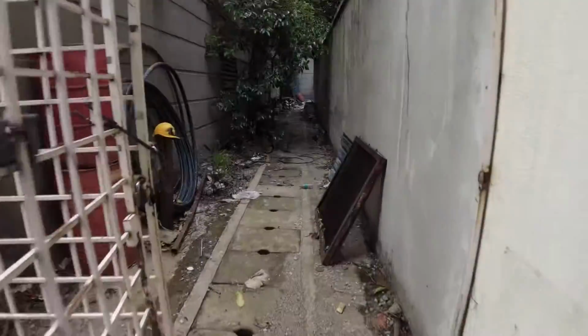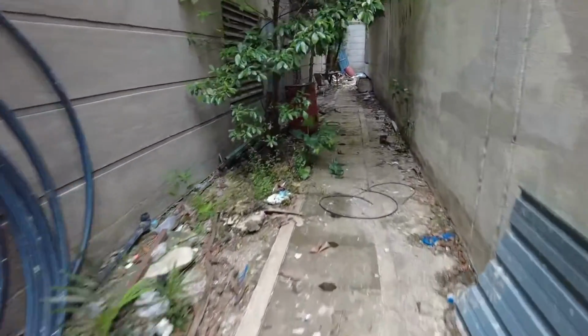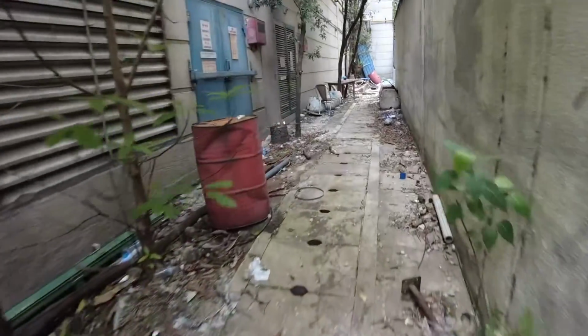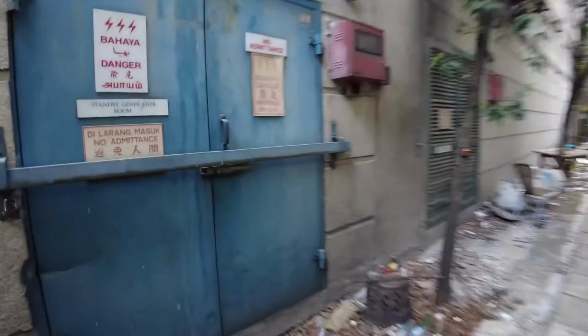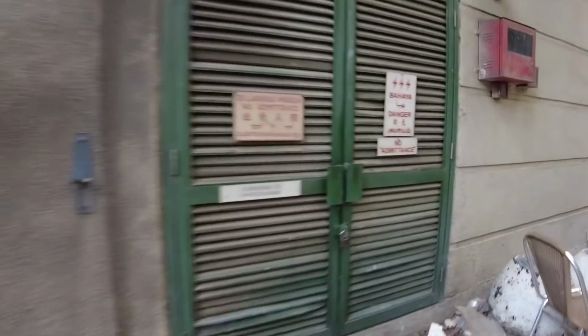Now we're going to check on the genset room and the LV room. Then we're going to test run the genset from the LV side at the ATS panel by simulating the signal. Now we are on the way to the Ritz Carlton residence LV room and genset room. This is the genset room. This is the LV room.